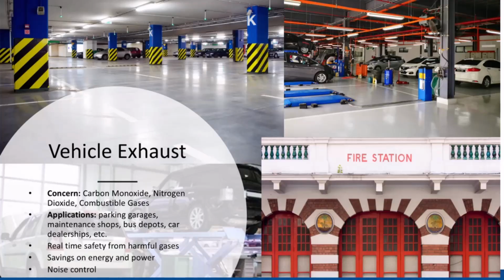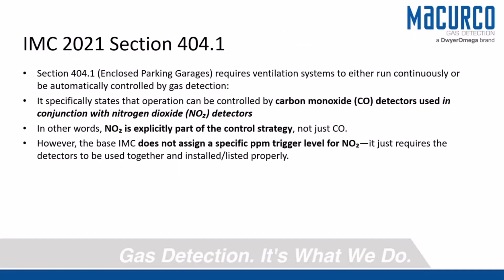I'm going to fast forward a couple slides here. The code is based on the International Mechanical Code, which IFC has adopted, and the International Fire Code has adopted. NFPA 72 has taken pieces of this and used it in their methodology as well. The concept is: if you choose not to run your ventilation system within these facilities all the time, it's due to installing a gas detection system. Long story short, it's very expensive to run your fans and exhaust systems, which are very large, all the time, 24/7. So you implement one of these, and now you're running at 10% or 20% of capacity within these systems. You're saving a lot of money on the back end, and a lot of energy at that point too. But basically what it says is the only way to shut your fan or ventilation down is via one of these systems. In some states, they require this to go back to the fire alarm panel, that's why our footprint in fire is so big.